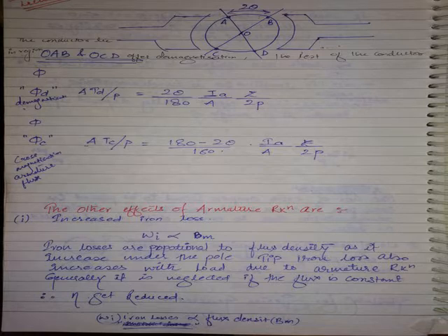Why you are going for this particular construction means, you have just discussed that the flux density is increased under the pole tips. So the increased flux density needs to be reduced to reduce the iron loss. Then, how to reduce the flux density under the pole tips? By only offering reluctance. If the reluctance is offered under the pole tips, then automatically the flux density will reduce. Reduce flux density but not flux. Is the point clear? Flux should be the same, density should be reduced.